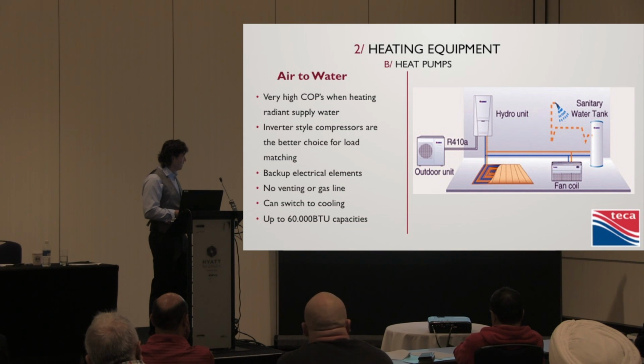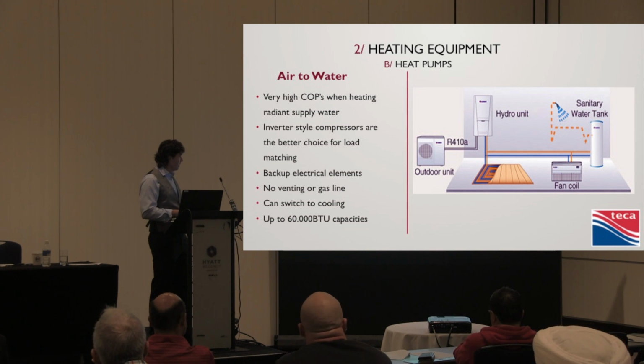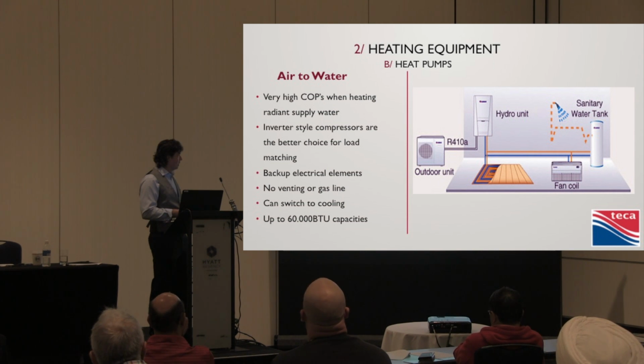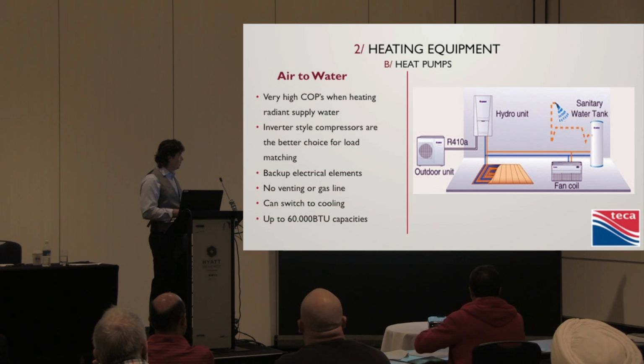Remember, radiant floors are very low temperature, so the COPs, the coefficient of performance, with these things is huge. When you're trying to heat air, if this was the furnace and you had a coil in there, the temperature of the refrigerant you've got to get there is pretty high. When you're trying to heat this radiant floor, say to 85 degrees Fahrenheit, the performance goes up quite high. So these are actually a good unit.